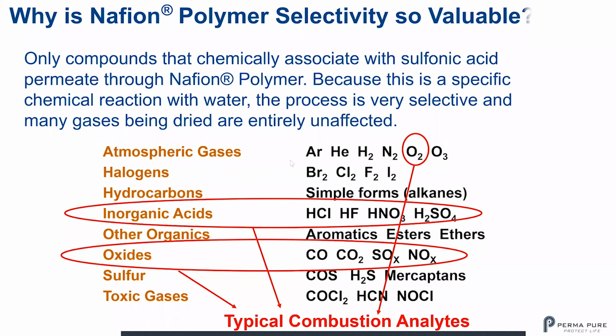proven so effective. The other part of it also is that because it's based on Teflon, it is also totally chemically resistant to any of these compounds as well. So not only do you have the ability to remove water without affecting those compounds, the material is very corrosion resistant to any of the type of nasty corrosive gases that come off a smokestack. They're not going to affect or corrode the Nafion tubing.